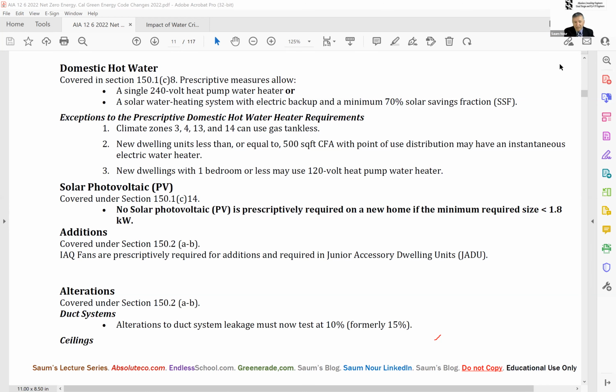You could be at your mother-in-law's and these fans will still be continuously operating. There are two ways: a whole house fan, or bathroom fans like Panasonic, Air King, and others, which work in two modes. One is continuous operation taking CFM out, with the code minimum generally at 20 CFM. The other uses a motion sensor in the room, taking 6 to 10 air changes to remove fumes and odors.